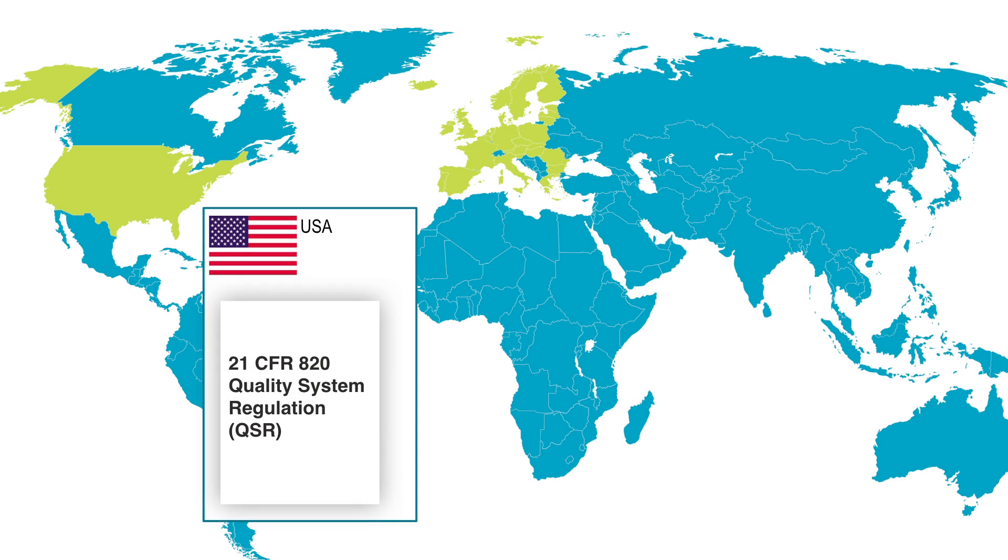As you may know, there are a lot of requirements that apply to medical device manufacturers. To be honest, they can appear somewhat overwhelming at times. Luckily, the requirements we will be looking at during this course will take you really far. Let's break them down. In the U.S. there is a regulation called 21 CFR 820, or Quality System Regulation, or just QSR, which is maybe the easiest thing to remember. That establishes requirements for manufacturers that want to sell their products in the U.S. market. This is the regulation in which you will find the subpart on design control.